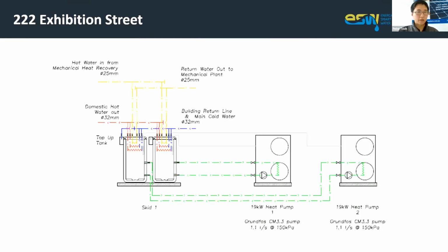This schematic drawing shows how the system is laid out. As you can see, we've got a heat pump to heat up the storage tank. At the same time, we've got a mechanical line, the orange line, that heats up the tank. The mechanical line usually runs at a higher temperature, somewhere around 70 to 75 degrees Celsius, so we try to capture that energy as much as we can to heat up the tank. And if the tank drops in temperature to, for example, 60 degrees, then the heat pump will top up the temperature to 65.